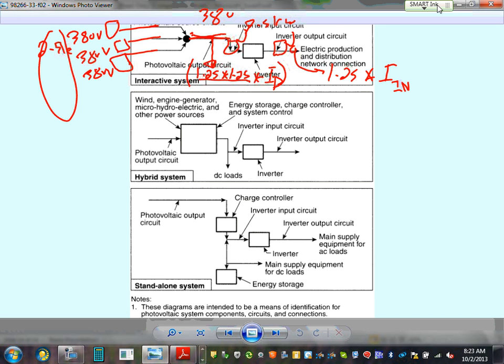The conductors can handle a short circuit. You do have to have ground fault protection, though. Didn't they say it was dangerous because the short circuit currents are so small but still really dangerous? Yes, they're a very small amount, but it's a fire hazard. The short circuit there is a fire hazard. I believe the photovoltaic system will be able to detect some of these short circuits, but they want you to size the conductors to be able to handle it, not to burn.